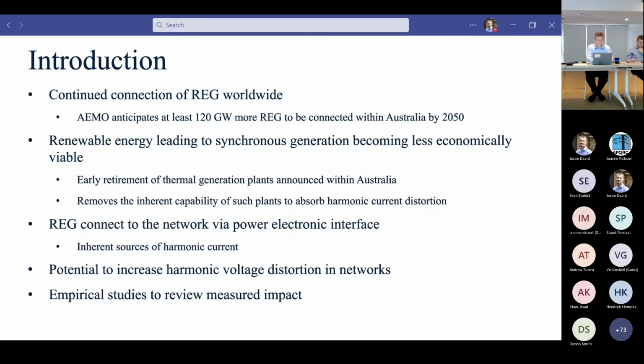And so that will ultimately remove large synchronous machines that exist on the network, acting almost as sponges of harmonic current, capable of managing the harmonic voltage in the network. So what we're seeing is that networks are becoming weaker, which will have an impact on the harmonic impedance of the network.